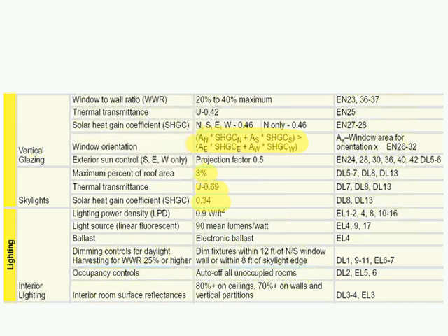When we did this, we didn't use the second generation of electronic ballast, but they will save you an additional maybe 5% to 7% energy if you're used to that second generation electronic ballast. We are recommending that you dim the fluorescent fixtures within 12 feet of the north-south windows or within 8 feet of the skylights. If you put skylights in, you're going to need to dim them.